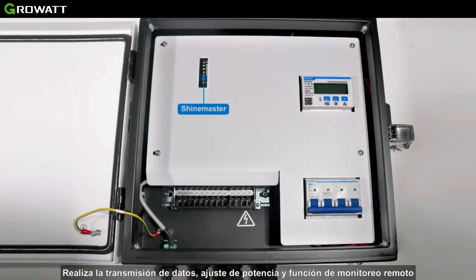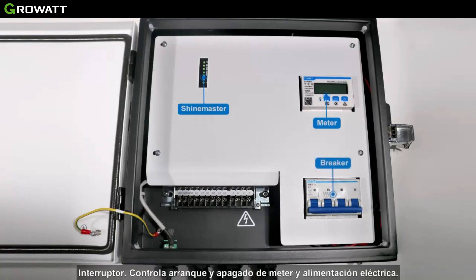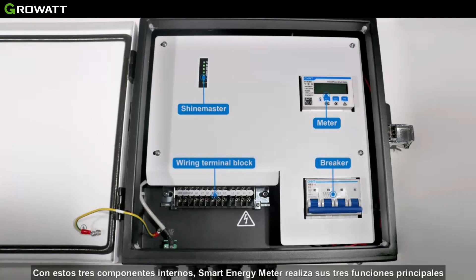There are four parts inside the Smart Energy Manager. ShineMaster, the control core, can realize data transmission, power adjustment, and remote monitoring functions. The status LED is used to display the running status of ShineMaster. The meter provides real-time monitoring of voltage, current, and function parameters. The breaker controls the start and shutdown of the meter and power supply.